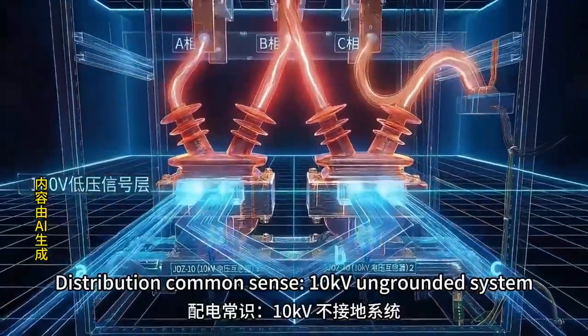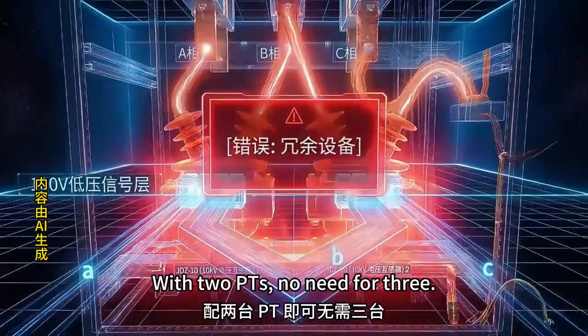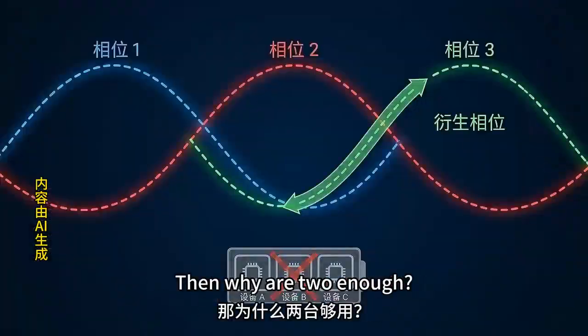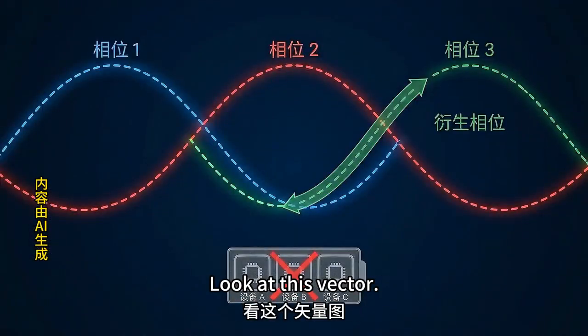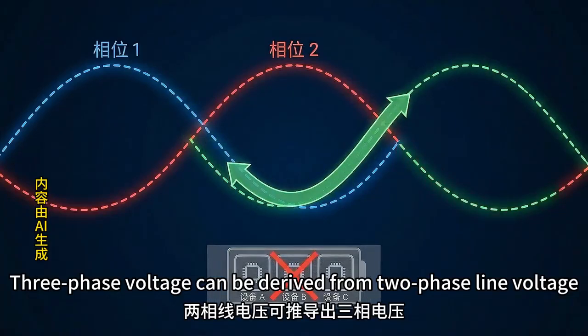Distribution common sense: in a 10 kV ungrounded system, 2 PTs are enough, no need for 3. Then why are 2 enough? Look at this vector — the 3-phase voltage can be derived from the 2-phase line voltage.